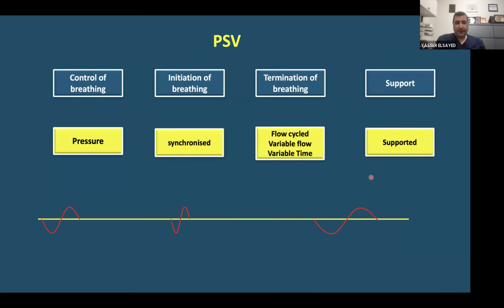So PSV, now we can see the patient breathes with variable I time. The infant might take a sigh, might breathe with a really long I time and long expiration, and can do small breathing, and the machine is following exactly. So it is pressure controlled, with synchronized initiation. The I time is variable according to the patient's needs. So the patient can terminate the breathing at any time according to his own I time.